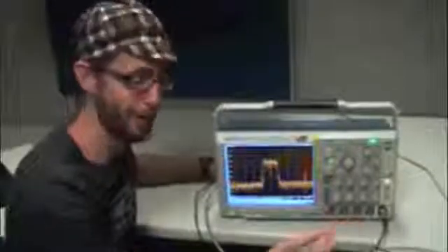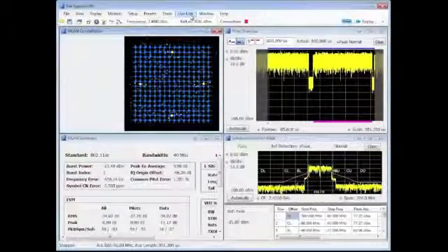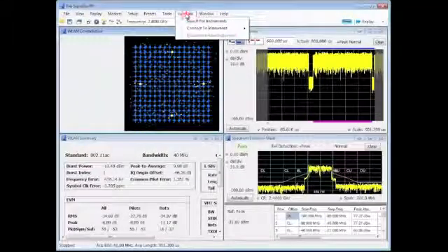We've got an MDO4000B oscilloscope. It's got a wireless LAN signal going to the RF port. We've tuned it to the right frequency. We can see that, yes, indeed, there is a signal there. So now we're ready to take the device end of our USB port and plug it into the back of the MDO. Then we plug the other end of the USB cable into the laptop. Then we go to the Live Link menu and we choose Search for Instruments.